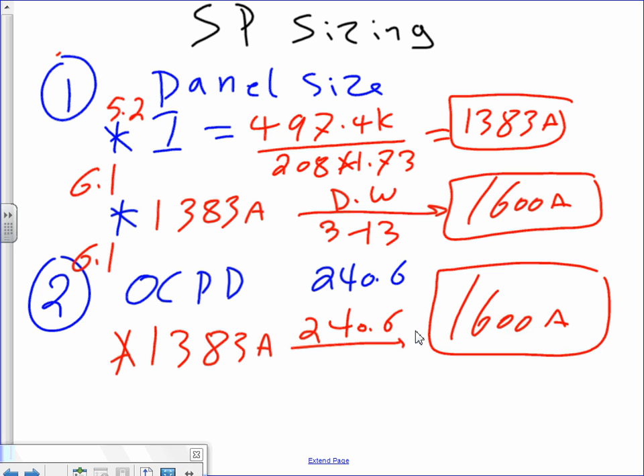Okay, very easy. You take the 497.4K divided by 208 times 1.73. Everybody knows why? We're finding the amps. And that's the amount of amps that you have. 1,383 amps.